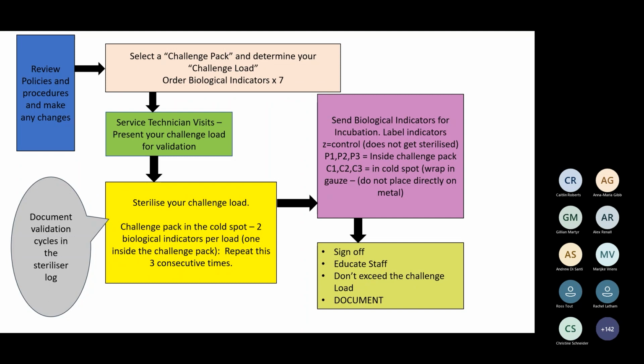So you select a challenge pack and determine your challenge load. A challenge pack is the pack with the most instruments, the most dense pack that you would process every day. And then that pack would be within your challenge load. Your challenge load is basically the most instrument sets that you will process in the sterilizer at any given time. You need to make sure when you're ordering your performance qualification on your machine that you also have your biological indicators for confirming your lethality.